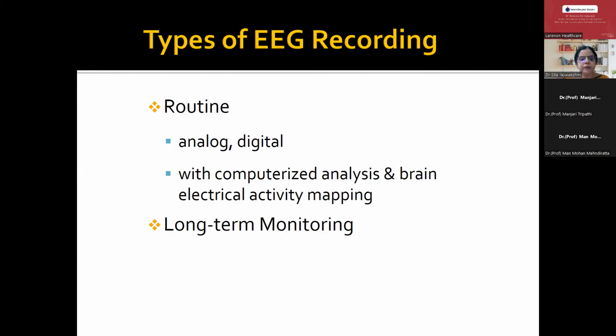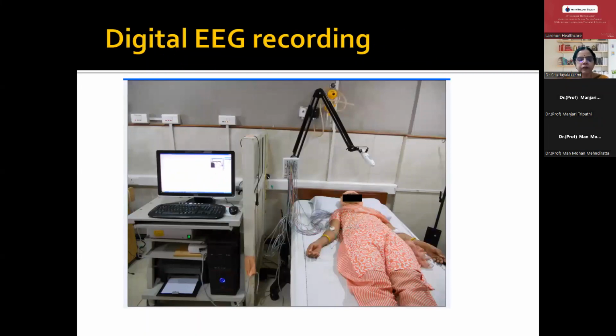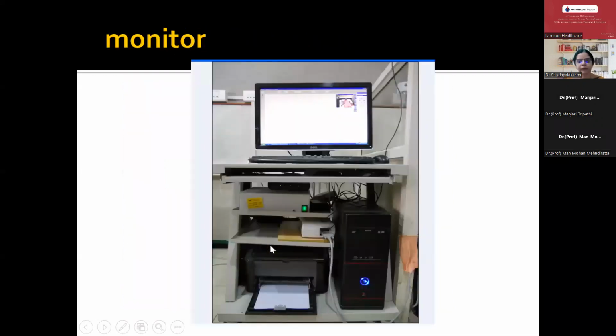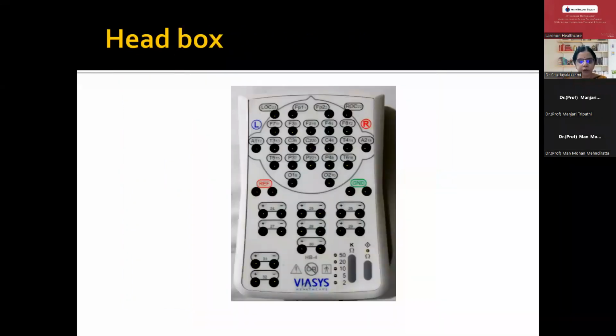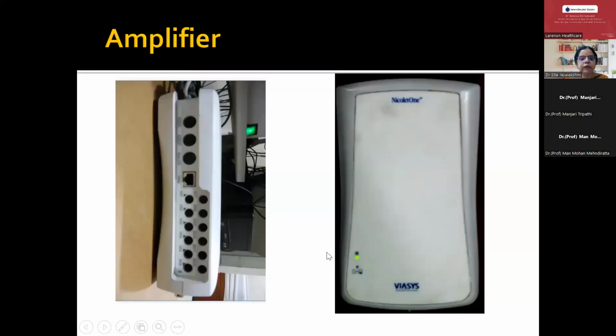And we can use these machines even for long-term recording, where it varies from 1 hour to a few days to almost 7 to 10 days based on the indication. This is the digital machine where you can see this is the monitor and this is the CPU and this is the junction box, and also the electrodes which are connected to the brain, and this is the photic stimulator which is attached to the same portion. And the monitor, if you look at, this is the very important part, which is the head box, where you can put the electrodes which are numbered very conveniently. So whatever the electrode is, it can go into that slot. And nowadays, this is the amplifier which amplifies the EEG signal.